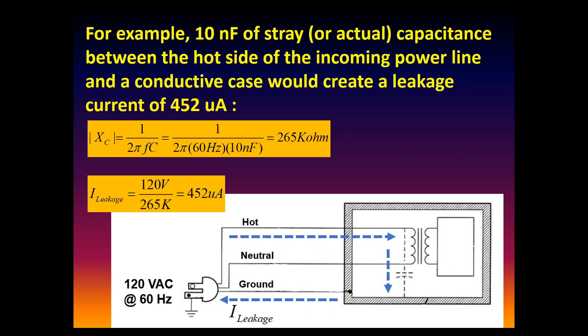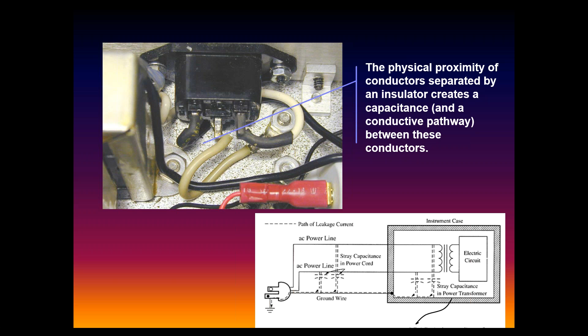You can replicate this using a physical capacitor too, and you get the same thing, because real capacitance is just the sheer proximity of conductors. You've got hot conductors physically next to a case, and this is inversely proportional to the distance between the conductors. The farther away, the less capacitance; the closer to the case, the more capacitance. So there's nothing wrong with the circuit, it's just the inherent way in which it was designed and built.